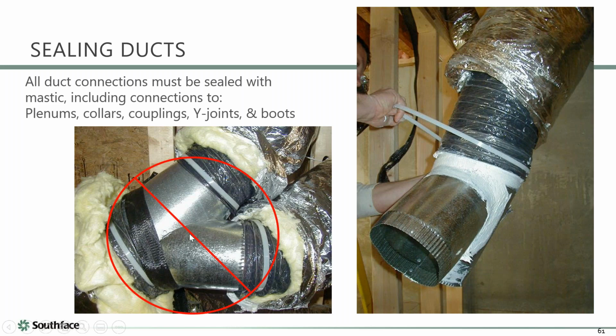The other thing is, we always recommend you inspect some of the fittings like Ys and things like that, because this is people getting lazy, thinking, I'll just cover it up with insulation. You can see no sealant was used at all. Also, if you look at the amount of crimp, see this distance right here, you can see that this zip tie is actually off of the duct. This is going to disconnect in time.